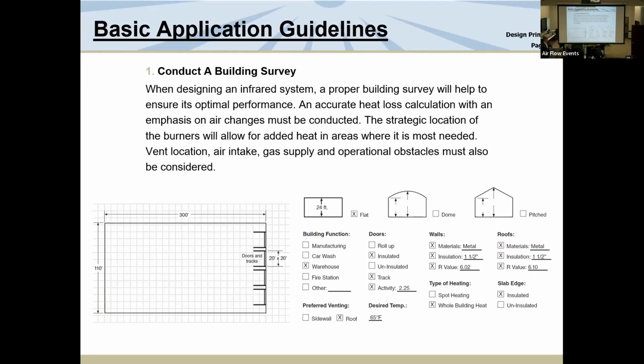But when we're doing a survey for infrared, I want you to look at: are there cranes in the building that might park right below a heater? Are they going to put racking up or down? The racking is going to have stuff stored too close to the heater. Are there sprinkler systems in the space that we need to work around? There are a lot of things that, with infrared, because of how it works, we have to consider in this first phase. All right, next slide.